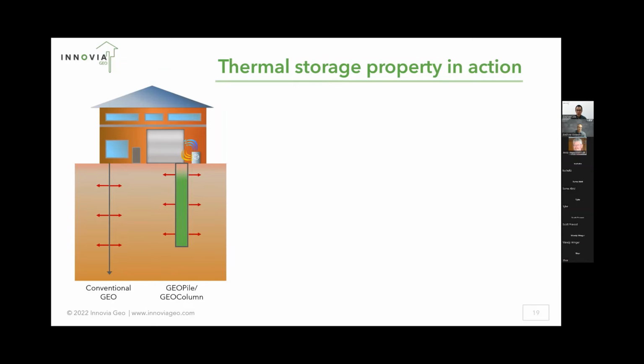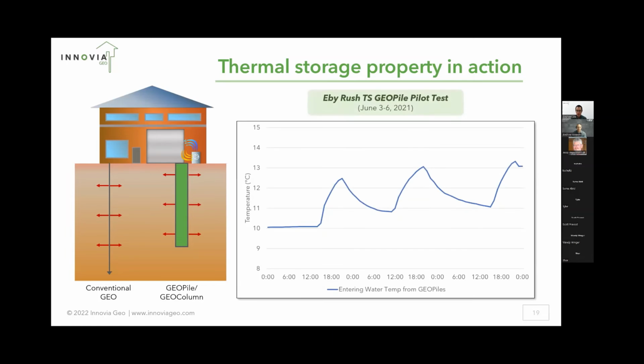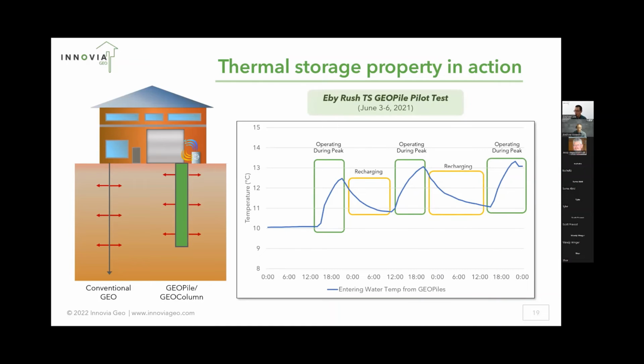And so that we're getting that temperature at a better state so that it can operate more efficiently and provide the heat pump with a more stable operating temperature. And so here's an actual result from testing we did last summer where we did exactly that. So over 3 days, and they were 3 pretty warm days, we turned on our geopile system and let it operate at maximum during the peak hours of the day. So probably around noon to about, I think it was about 8 or 10 p.m. in the evening there. And then we shut off the system.